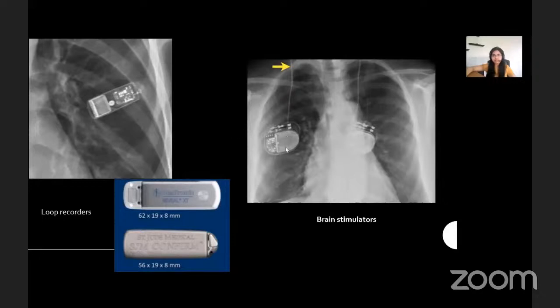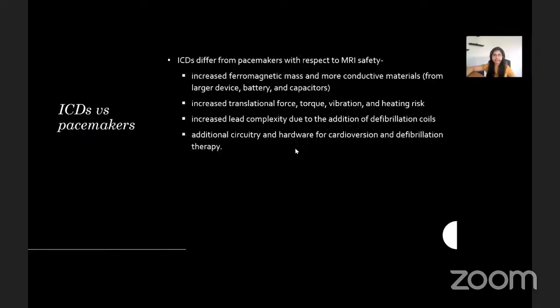Parkinson's brain stimulators have similar generators as cardiac pacemakers and are also placed in the subcutaneous chest; they should not be confused with pacemakers. Implantable cardioverter defibrillators differ from pacemakers with respect to MRI safety. Since they have increased ferromagnetic content and more conductive materials, they are susceptible to higher translational forces and torque. Additional circuitry and hardware for cardioversion or defibrillation therapy increases the potential sources of unexpected behavior such as device malfunction, unintended cardiac stimulation, or electrical reset.